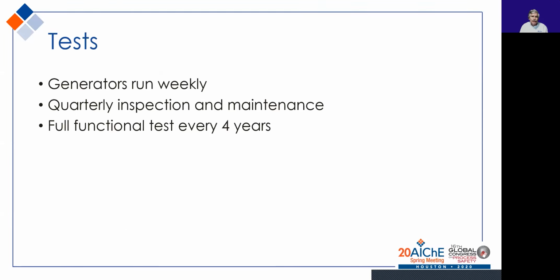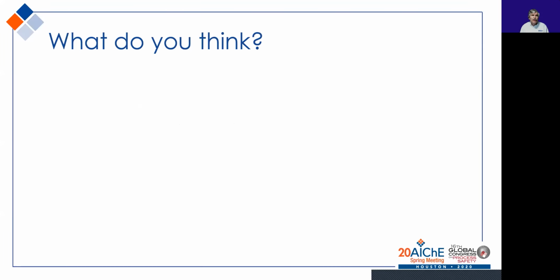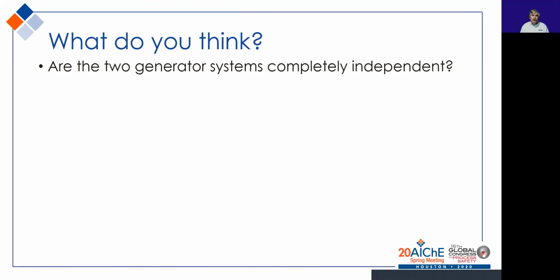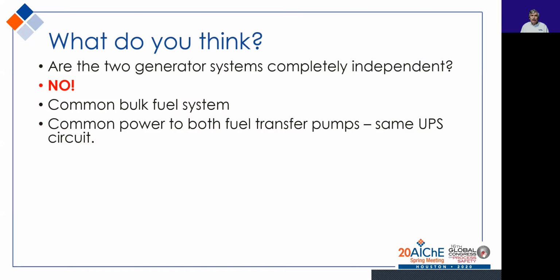When we test this system, we run the generators weekly. We have a quarterly inspection and maintenance. We have a full functional test every 4 years. So what do you think? Are the two generator systems completely independent?